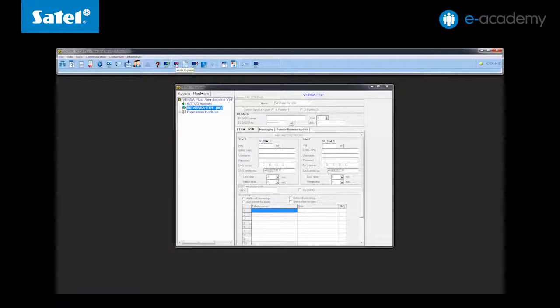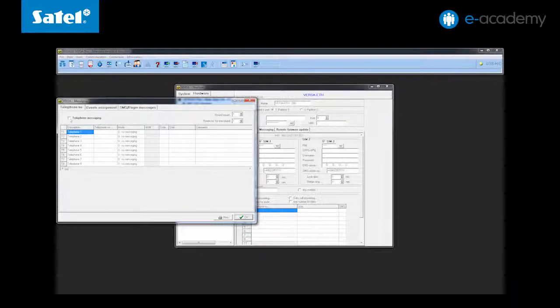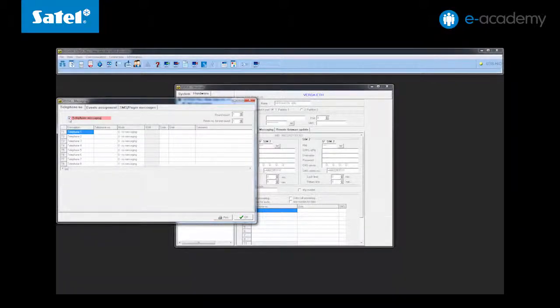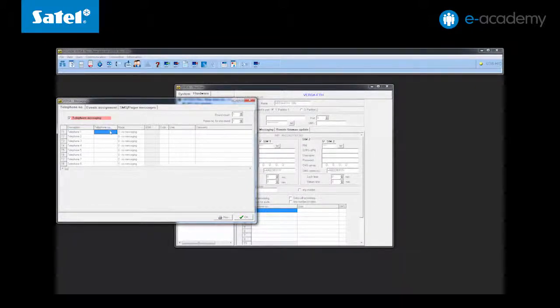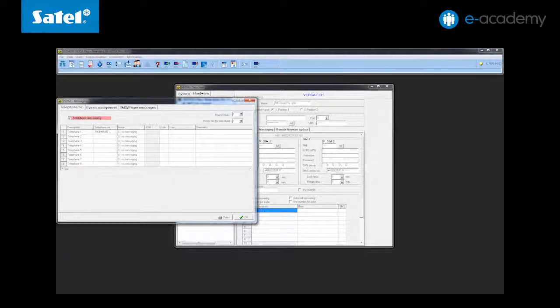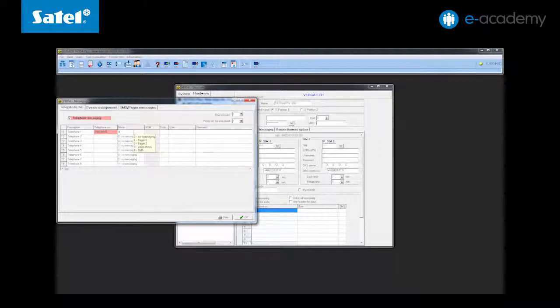Now let's go to the telephone notification. Enable telephone messaging by selecting this function and then enter the phone numbers to be notified. We will only enter one number but there are as many as eight phone numbers available. In the messaging type column select the fourth function that is SMS.